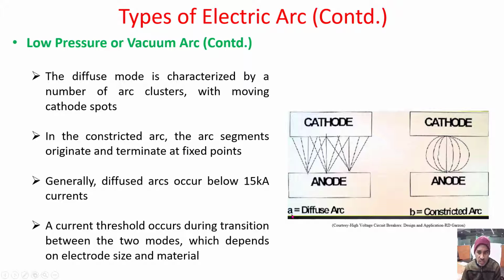So here it is, this is diffuse mode and this is constricted mode. The diffuse mode is characterized by a number of arc clusters with moving cathode spots. Here you can see the cathode spots are not fixed, but anode spots you can see here. In the constricted arc, the arc segments originate and terminate at fixed points. This is a fixed point, this is again a fixed point, this is a constricted arc.